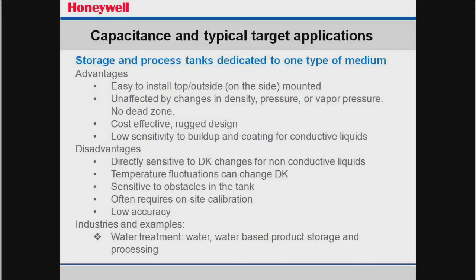It can be affected by obstacles in the tank that give you a false reading. And it often requires an on-site calibration. So somebody has to come in there with an empty tank and say, this is 0 level, and then fill it up and say, this is 100% level, which is not real convenient to do. It's not real accurate, but they're not real expensive either.